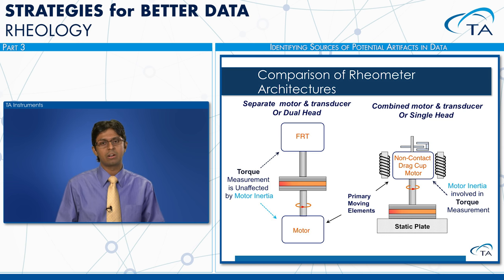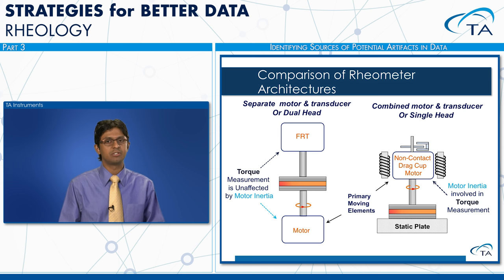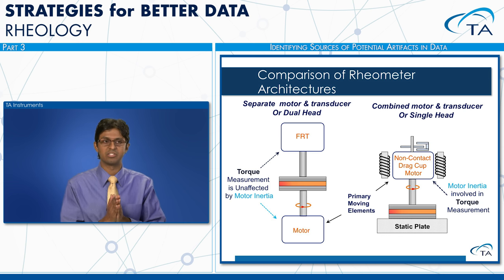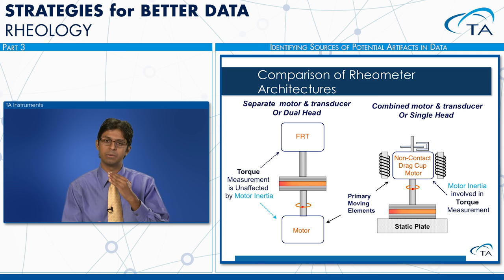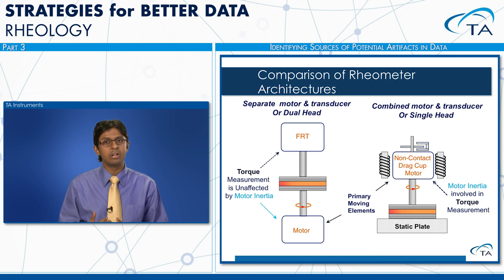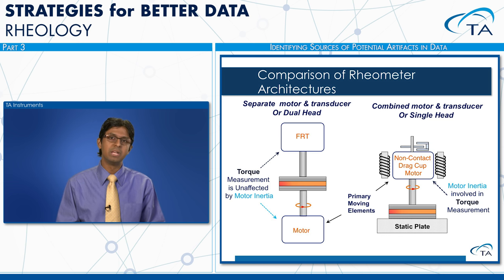In a separate motor transducer or dual head design, the motor moves on the bottom and torque is measured independently by a force and torque rebalance transducer, so the torque measurement is unaffected by inertia. With a combined motor transducer design, a drag cup motor applies torque, so motor inertia is involved in the torque measurement — making it imperative to minimize motor inertia as much as possible in the instrument design.